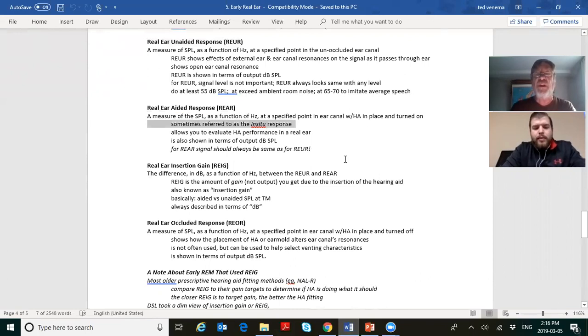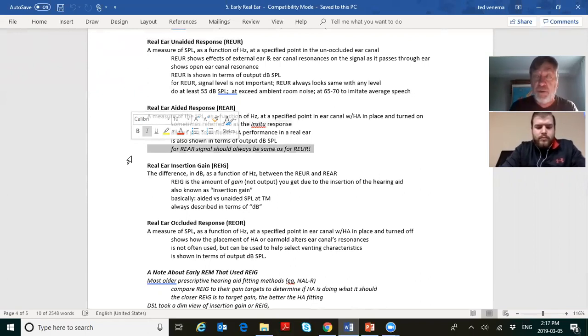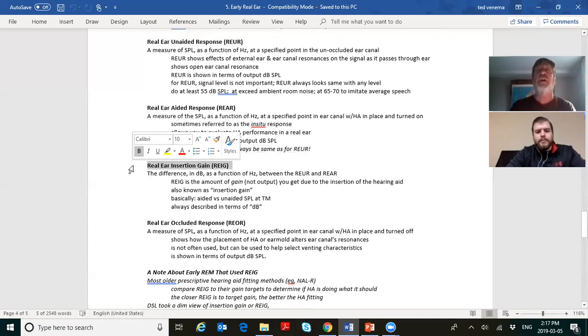When you see something called in situ, that's Latin for in situation. Sometimes it's referred to as the with hearing aid in place response, hearing aid in situation response. All right, the input signal. When you're doing REAR, and this is another classic mistake, when you're doing real ear aided response, your input signal has to be exactly the same as when you're doing real ear unaided. Otherwise, you're comparing apples to oranges. So if you used 55 dB SPL coming into the hearing aid doing REUR, you've got to use 55 across the frequencies when you're doing real ear aided. The difference between the two was called real ear insertion gain.